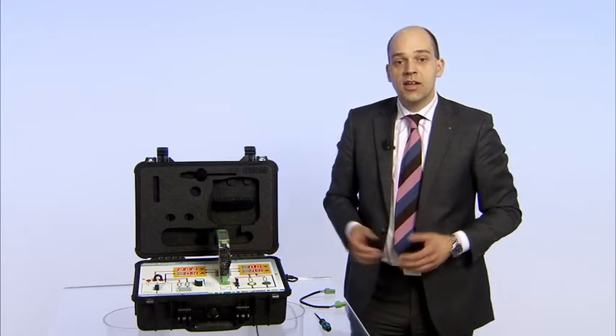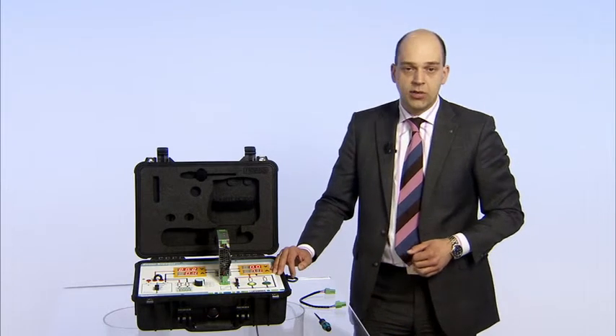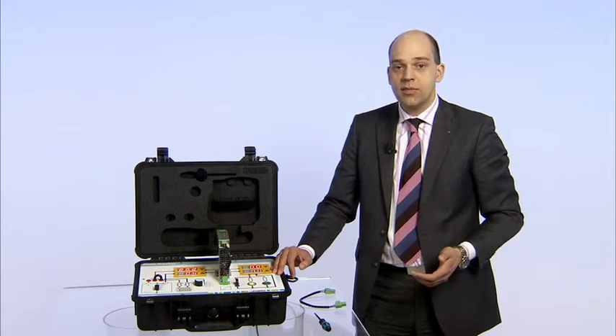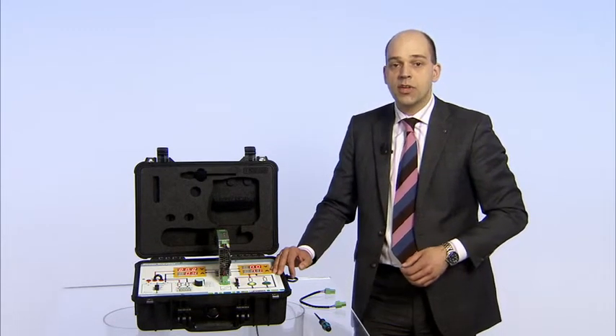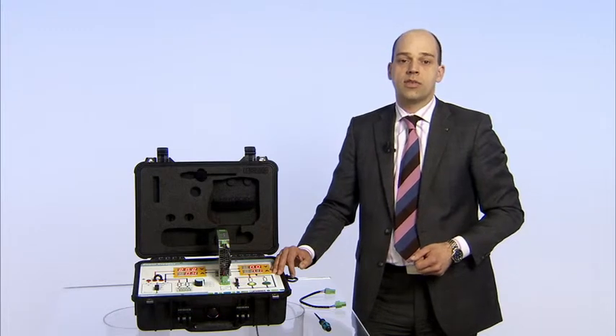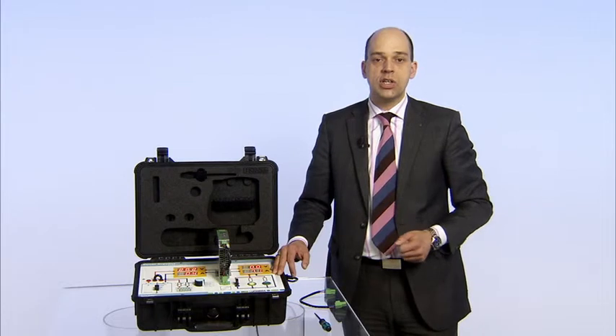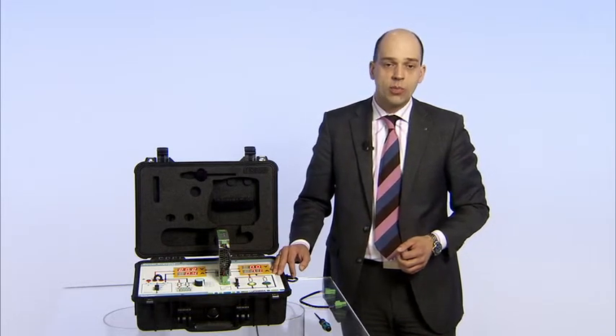As the first of their kind in the world, Quint Power DC-DC converters are equipped with patented SFB technology. In the event of an error, the circuit breaker is triggered swiftly and safely. Only the defective current path is selectively shut down, while the rest of the system continues to run. As such, the SFB technology dynamic power reserve supplies 6 times the nominal current for 12 milliseconds.